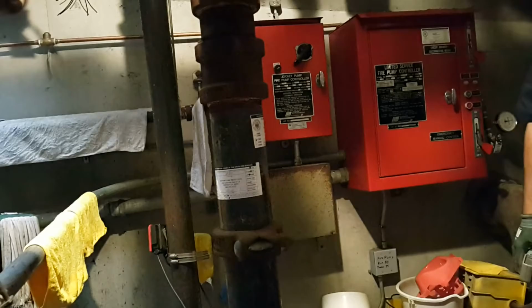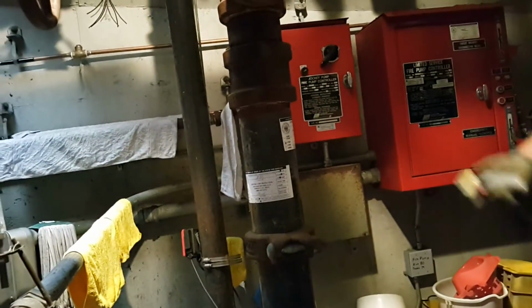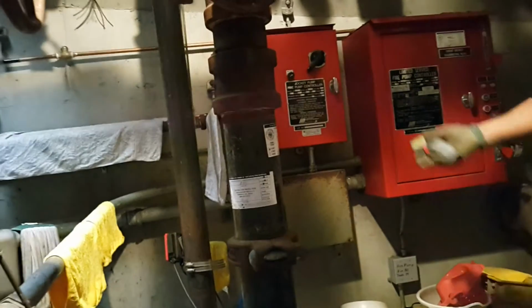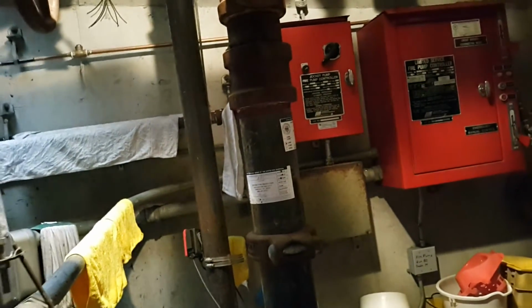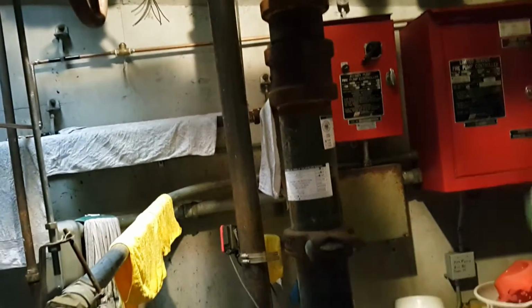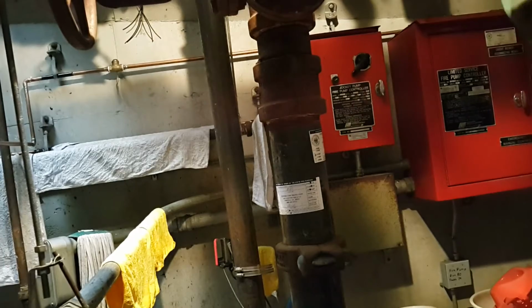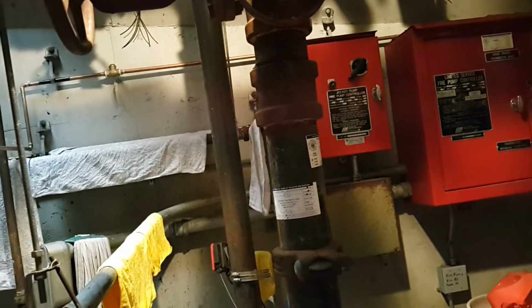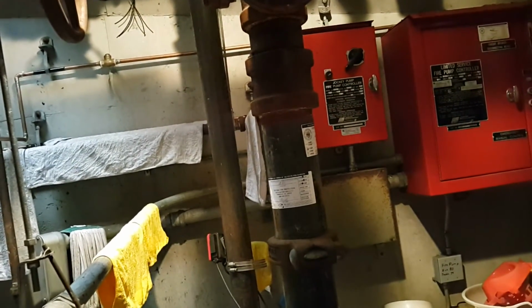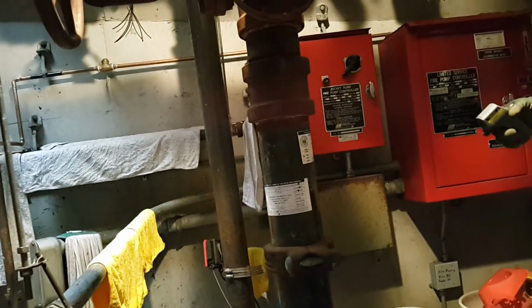But what if you're not there? They want you to come in and turn it off manually. That's their code. But our code for San Francisco is 10 minutes, and it has a timer. No, San Francisco wants the timer off. The State of California wants a timer in there. Remember, cities can only go stricter than the California code. They can't go lighter.